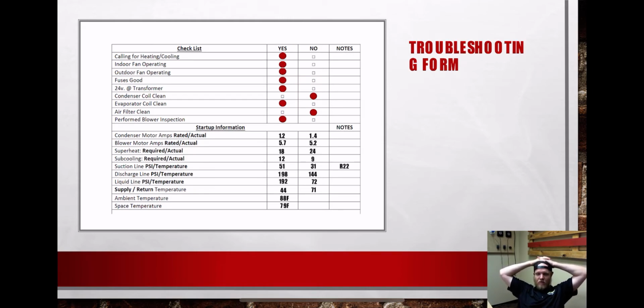What are you there for? No heat call, no cooling call. What are you there for? Is the indoor fan operating? Yes or no? Is the outdoor fan or fans operating? Yes or no? Are the fuses good? So that means, did you check continuity from the top of the fuse to the bottom of the fuse? Do you have 24 volts at the transformer? Check right at your transformer.